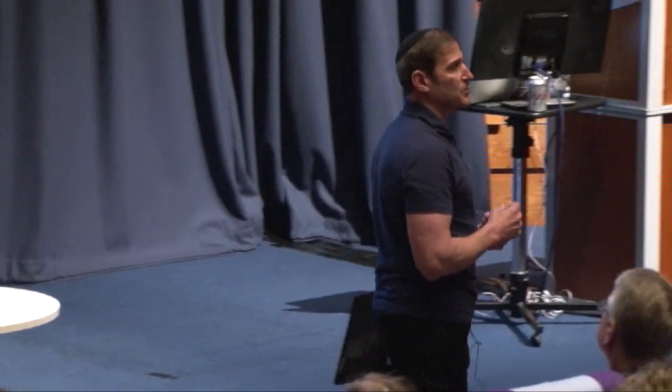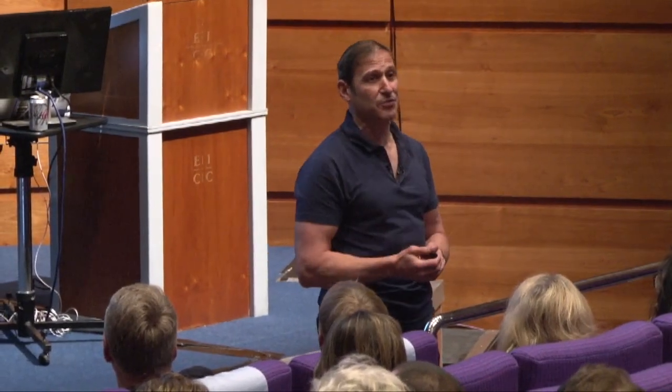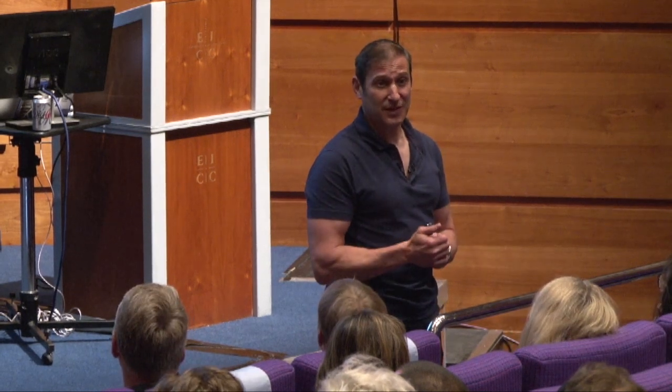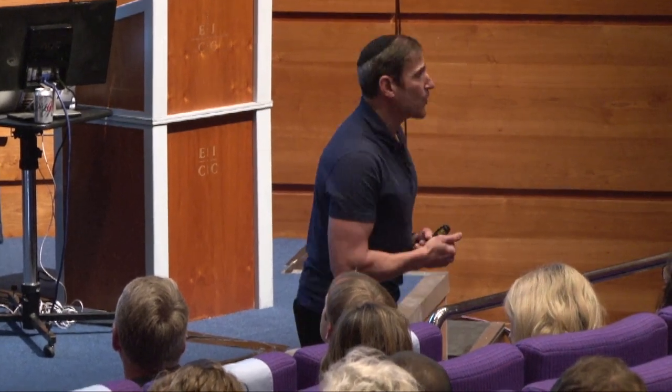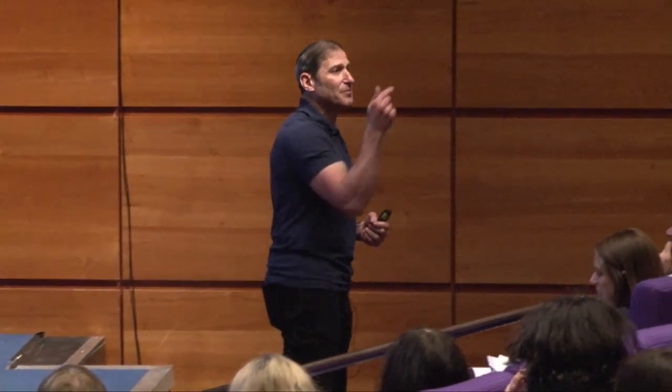Certainly diffusion-weighted imaging. If you're doing an imaging sequence and it takes you a minute or less, you know you're using extremely rapid gradients, right? For most systems out there, you can't even control directly what that gradient dB/dt will be. It's defaulted by the manufacturer. Some of the manufacturers now have, one of them is already out with it as a product, you can say, do not exceed this amount of RF, do not exceed this amount of dB/dt, and it won't. Others are going in that direction as well, which is good for us.